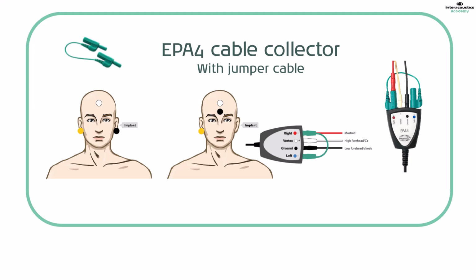It is also possible to use a jumper cable with a 4-electrode cable collector, which effectively removes one of the electrodes from play and allows you to perform the testing with just 3 electrodes. This is easily achievable when testing a unilaterally implanted patient, and is the methodology of choice in the majority of published research papers into aided cortical testing with cochlear implants. For a bilaterally implanted patient, it is possible to explore testing with 4 electrodes and both implants switched on. But if artifact is present in the waveforms, then switching to unilateral assessment with 3 electrodes is the recommended process in these cases.